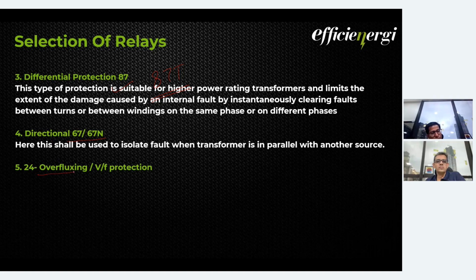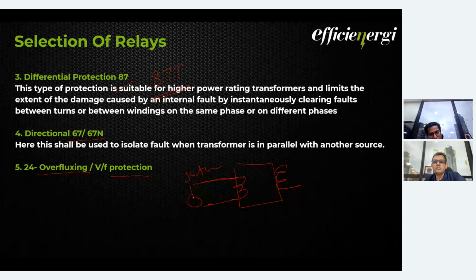There is an overfluxing protection. Now you must be knowing what overfluxing is and how overfluxing can be damaging. Overfluxing means saturation. This is your transformer, this is your secondary, this is your primary. Now what happens in reality? You apply the voltage, then a magnetizing current flows. The magnetizing current is very low because there is a generation of a back EMF. That EMF is induced because there is a d phi by dt.